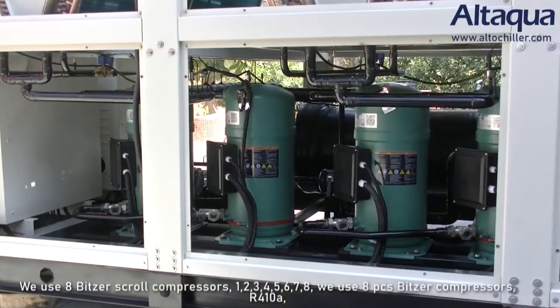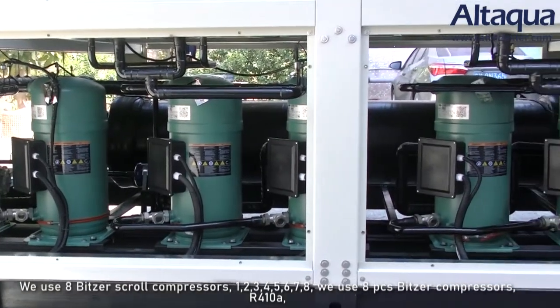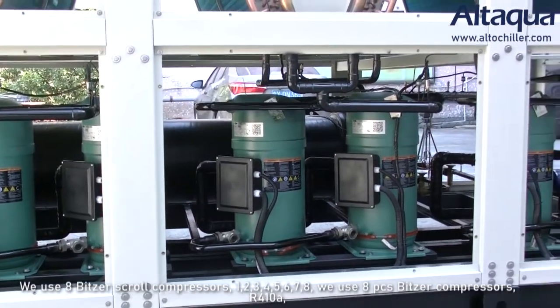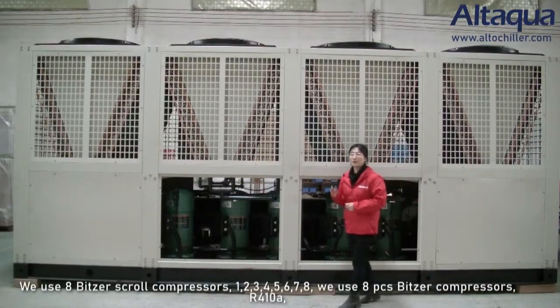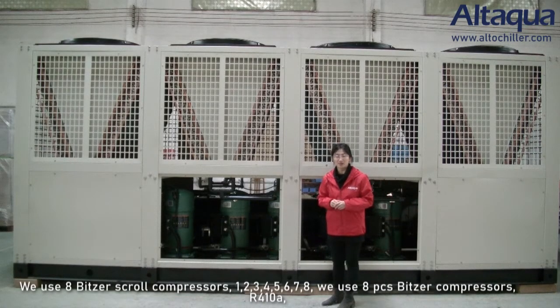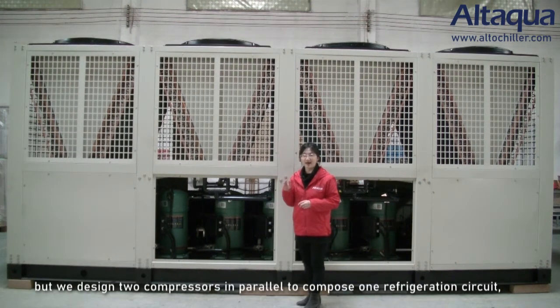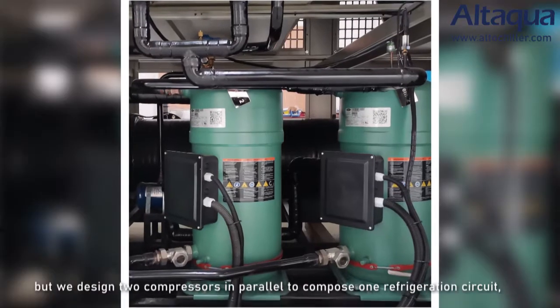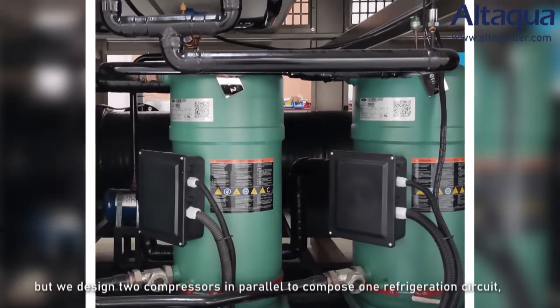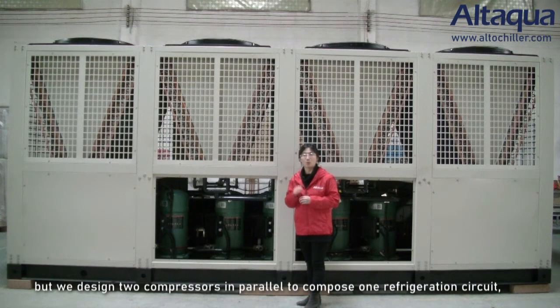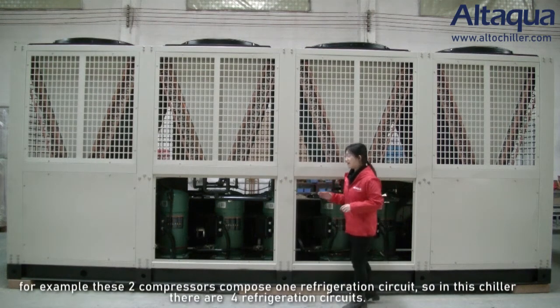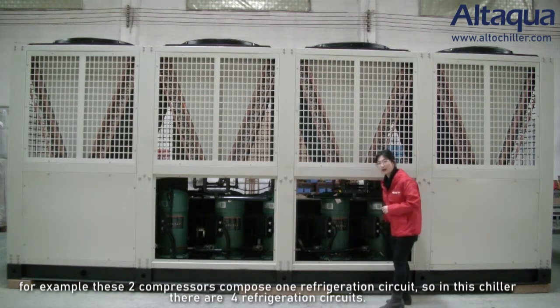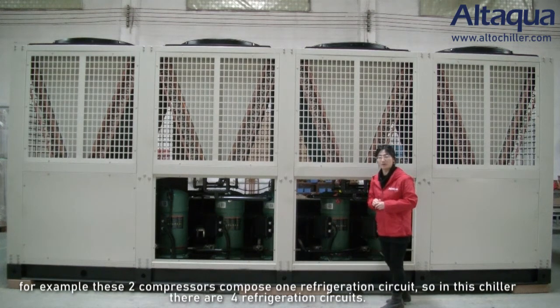1, 2, 3, 4, 5, 6, 7, 8. Okay, we cannot see that one. We use 8 pieces of Bitzer scroll compressors, R410A. Although we use 8 compressors, we designed 2 compressors in parallel to compose 1 refrigeration circuit. For example, these 2 compressors compose 1 refrigeration circuit. So in this chiller, there are 4 refrigeration circuits.